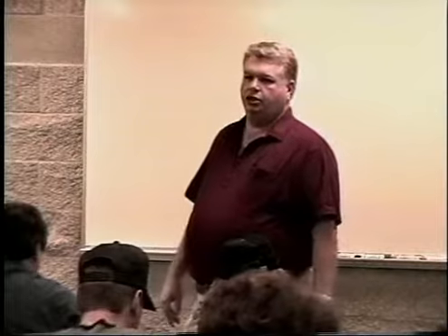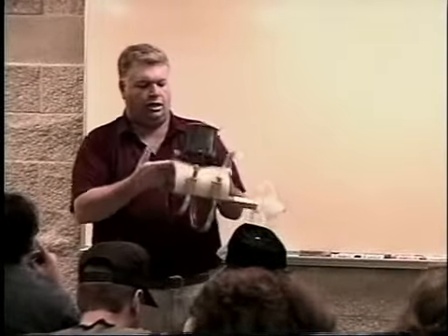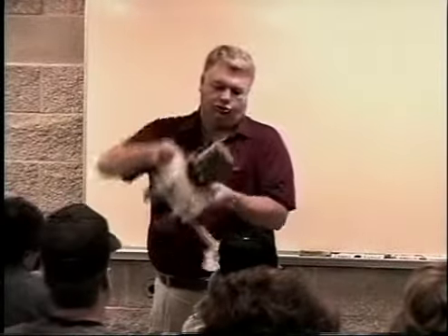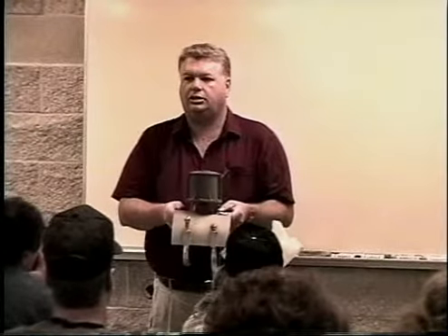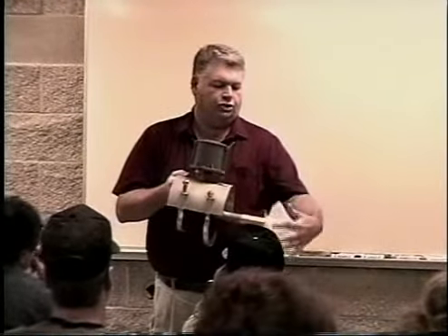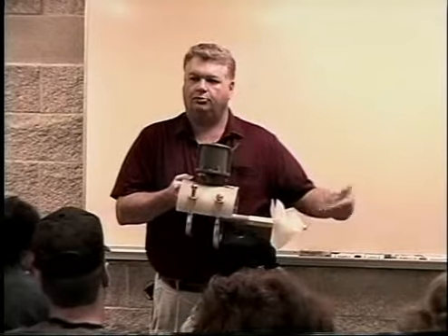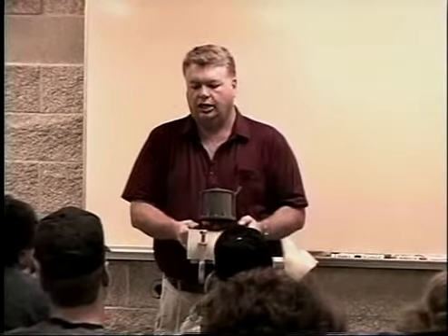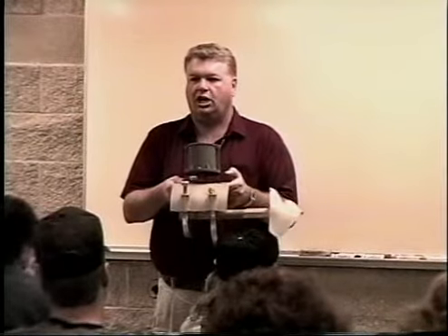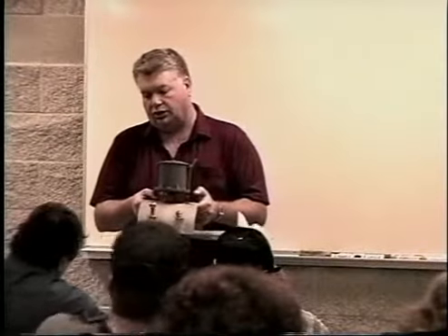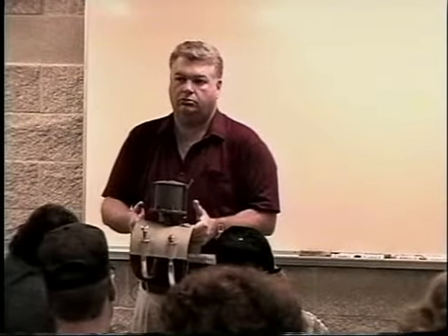Now here's a flow meter. One style is a propeller style. Thank you. And this would latch right on to an 8-inch pipe. Saddle clamp, you'd have to drill a hole in the top of the pipe, drop this into the hole, clamp it into place, and it's going to record, and this thing just spins. So as the water comes across it, it spins a propeller, and the speed of the propeller will tell us the velocity of the water in the pipe, and we know the cross-sectional area of the pipe. It's 8-inch diameter, so we can find the cross-sectional area times the velocity equals the flow.